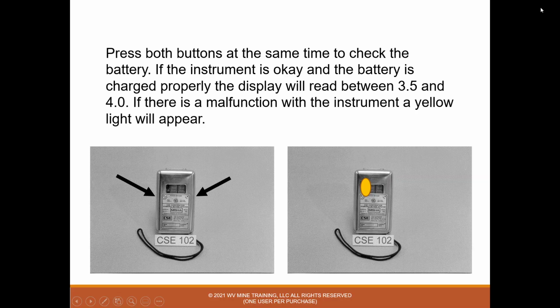You can see on the right-hand picture of the 102, I have this big yellow dot here, and obviously on the instrument that's going to be much smaller. I've just done this for instructional purposes, but a yellow light will come on. So when you do the battery voltage test, both buttons at the same time, if there's a malfunction with this instrument, this yellow light will come on. And I should say at this time, the CSE 102 LD, the large display, does not have this yellow light. It will not display a malfunction.